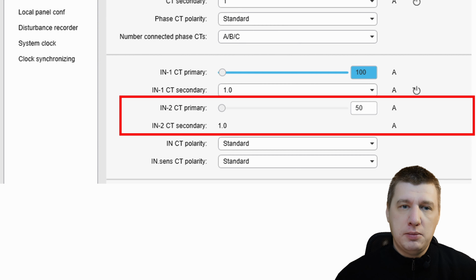they cause massive damage. In the software, look for the setting labels and match them exactly to the nameplate of your core balance CTs. If your CT says 50:1, type 50. It's that simple. Getting it wrong means your most sensitive protection doesn't work. So you should scale it correctly and your protection will work for the smallest hidden faults.